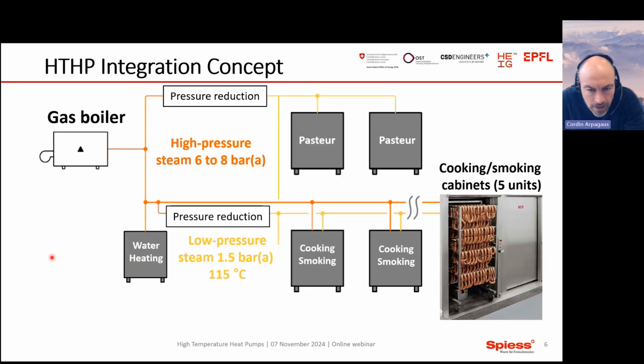So let's go more into detail. Now this is a schematic of how it looks. So they have a gas boiler and 2 pressure networks. One is a 6 to 8 bar steam pressure network with a pressure reduction. It goes into pasteurization processes. And then for a low pressure steam, they go into the cooking and smoking cabinets. They have in total now 5 or 7 units that are run continuously with different meats.